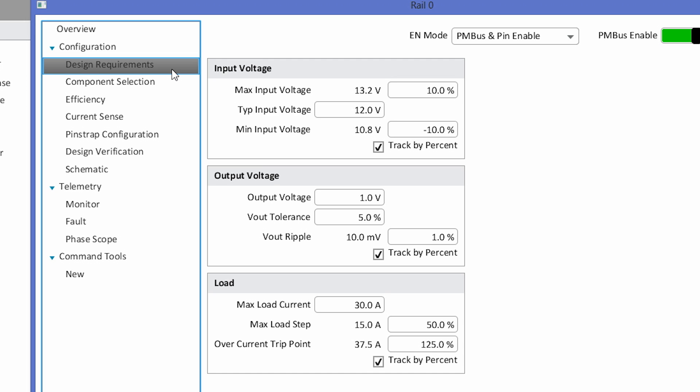The max load step is assumed to be one-half of the max load current, or 15 amps, and the overcurrent trip point is 125% of the max load current, or 37.5 amps.